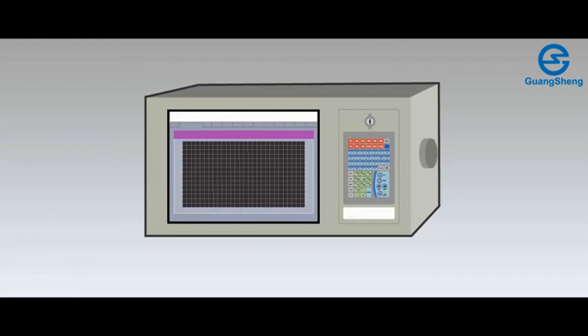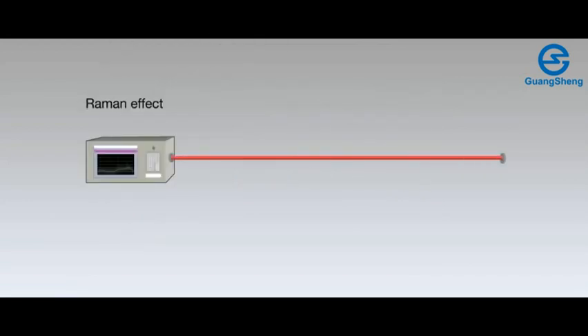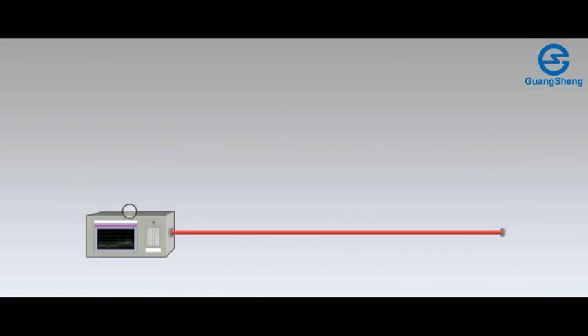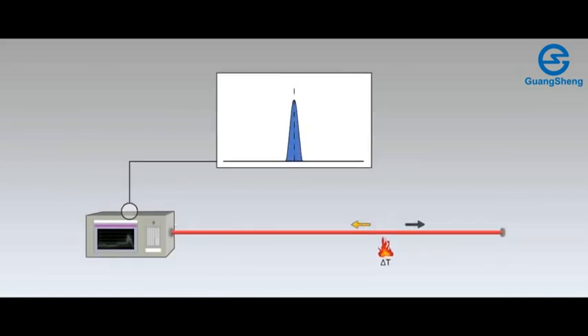The measurement principle is based on the optical detection of backscattered light induced by spontaneous Raman processes founded on OTDR techniques. The system performs multiple scans of the fiber and a larger number of averages while ensuring fast acquisition in the order of a few seconds with a spatial resolution of 1 meter.